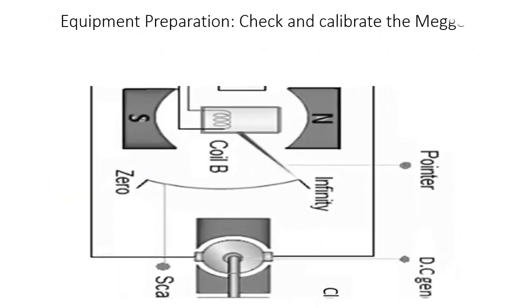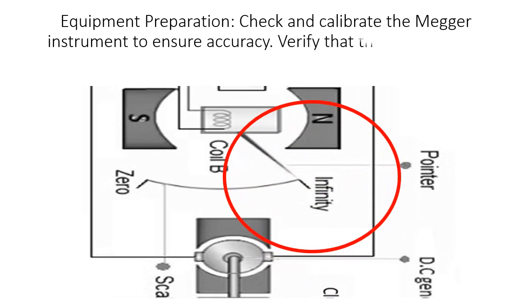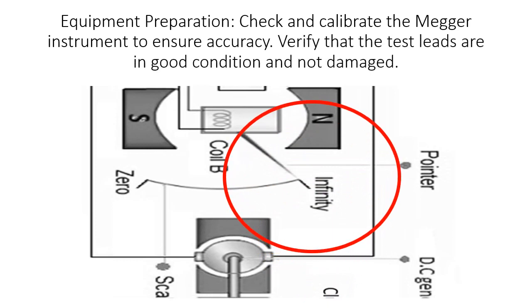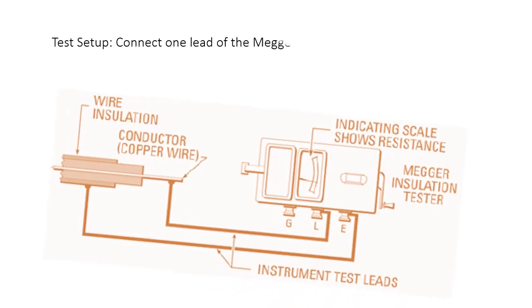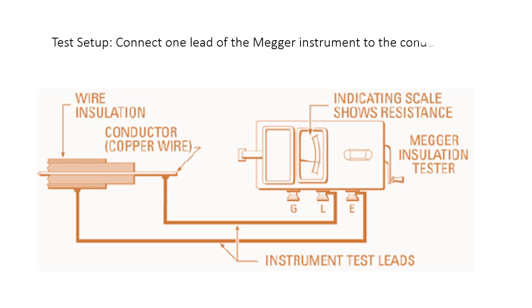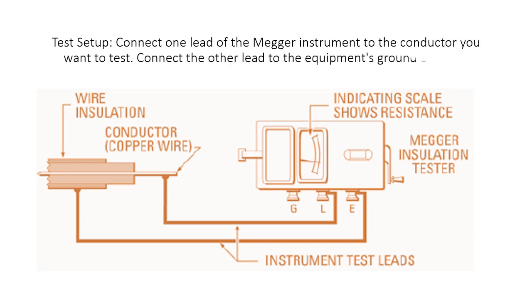Equipment preparation: Check and calibrate the Megger instrument to ensure accuracy. Verify that the test leads are in good condition and not damaged. Test Setup: Connect one lead of the Megger instrument to the conductor you want to test, and connect the other lead to the equipment's ground or earth.